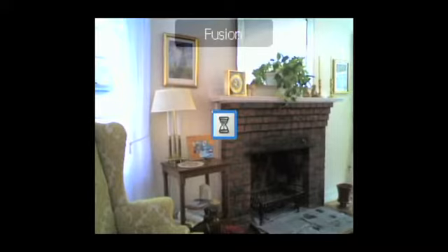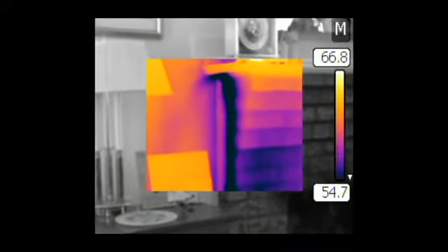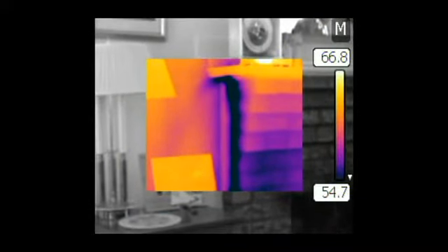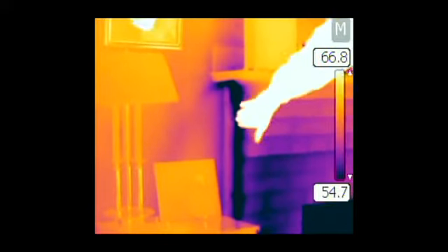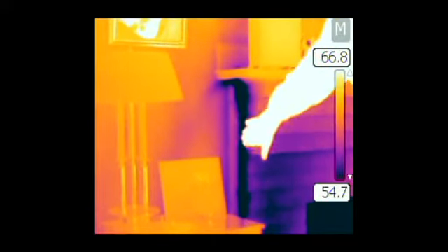We're back here in the family room, Fleming, where we saw before. We thought we could see some air infiltration from the seam where the fireplace meets the wall. Now, of course, the blower door is running, and it's very obvious what we got here. Definitely got air infiltration. Yeah, exactly where the framed wall structure meets the brick fireplace. There's some air gaps, and that could be a very simple thing to fix.